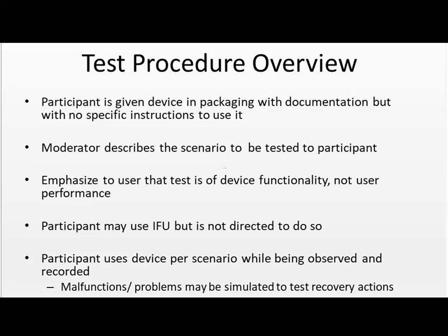You want the user relaxed, not thinking that he's being judged, but that it is the device that's being evaluated. During a test, the participant can use the information for use, but he's not directed to use it. It's his choice. The participant uses the device per the use scenario that's being tested, and he's observed and recorded.